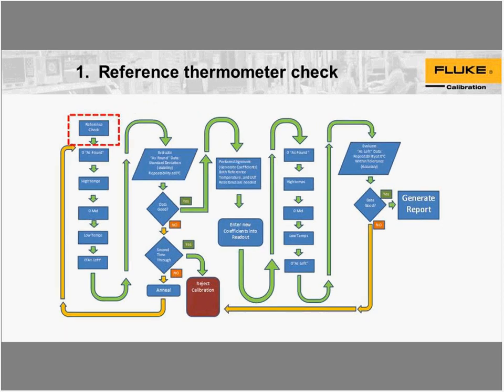The first one is the reference check. Okay, it's very important. If you don't know where your reference equipment is at the beginning of the calibration, how do you know if it's deviated by the end? It's better to take an as-found reading. And in my lab, we take an as-found reading, and then after we're done with the calibrations, before we start a new one, we take another reference reading. So it's always good to know exactly how your references are performing.